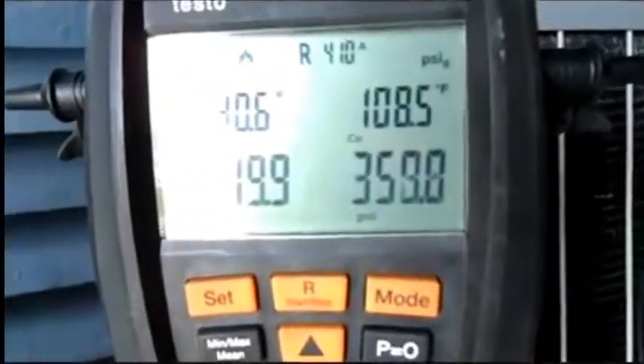And what you do is you look up your values for the temperature inside, which is close to 65. Our indoor airflow rate, which is 530. That's the rate we chose on the variable speed air handler. And outside we're close to 52. So according to that, we should be 345 and 121. Of course, we can be within 20 psi of the liquid side and 5 psi of the suction side. So if we look at that, we're warming up inside a little bit.